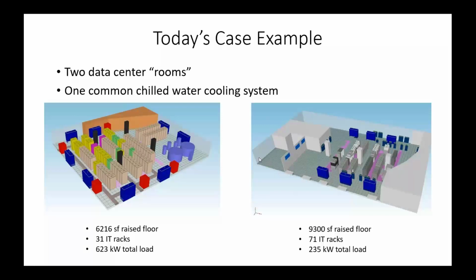These are chilled water. We're going to use a simple air-cooled chiller here for these two rooms. The room on the left is 6,000 square foot. It's got 31 racks, about 623 kW. Over here on the right, this one is a little bit funky. You'll recognize this because it's got crazy walls and it's got partially filled cabinets. This one's a little under 10,000 square feet, 71 racks, 235 kW. So we're looking at a total here of about 858, a little under a megawatt of power going into these rooms.